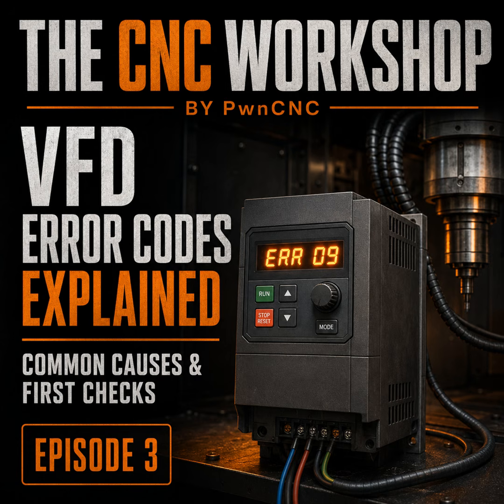Fourth example, ERR38 appeared after a coolant leak near the spindle connector. Disconnect power, allow the VFD to discharge, and inspect for moisture or contamination. Do not keep testing the spindle. That is a possible output phase short, not a "maybe it'll dry while cutting" situation.